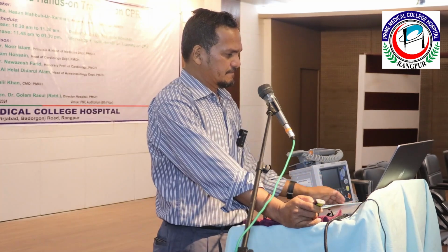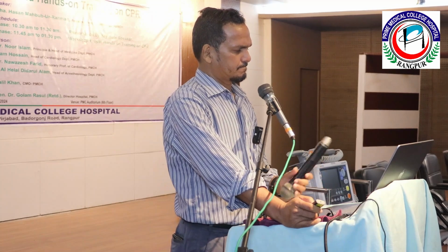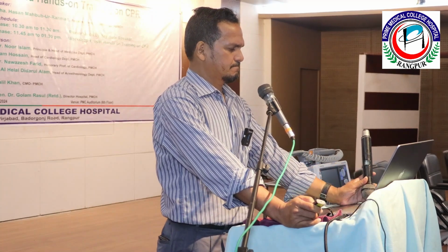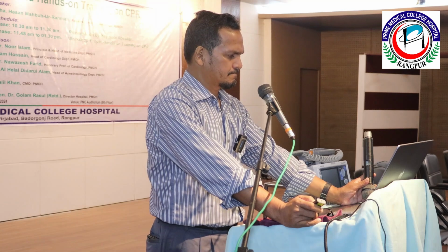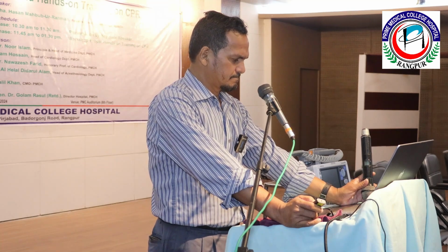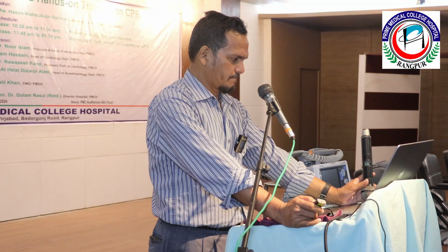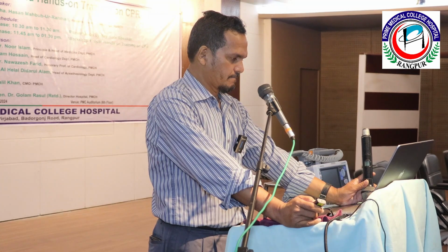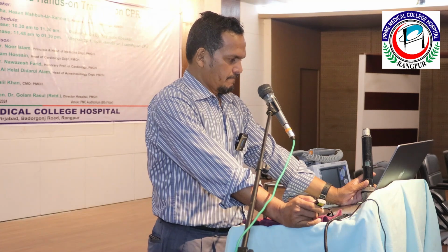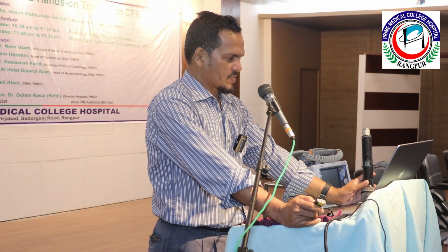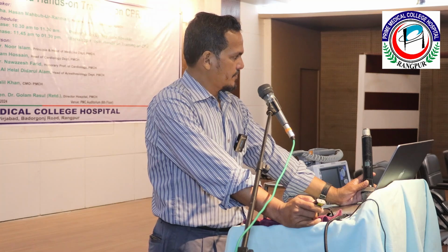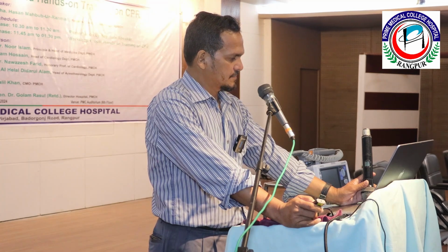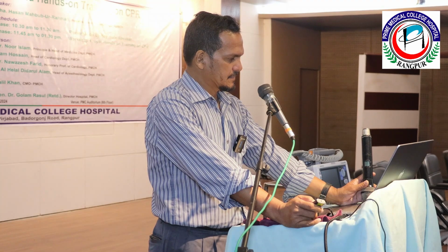This is the Defibtech. During an emergency intervention, any life-saving technique is going to require a high level of excellence in its delivery. The Lifeline ARM, Defibtech's latest technological innovation, is an automated chest compression system that, as an adjunct when effective manual compressions might not be possible, consistently delivers at least 2 inches of depth compression at a rate of at least 100 compressions per minute, as advocated by AHA and ERC guidelines.